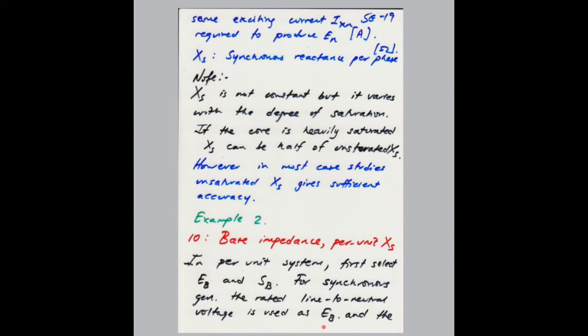Just take note that the synchronous reactance of the generator is not constant. It varies with the degree of saturation of the machine. So if your machine is getting saturated, the value of Xs will be lower. If it's heavily saturated, for example, the synchronous reactance can be half of the unsaturated value.